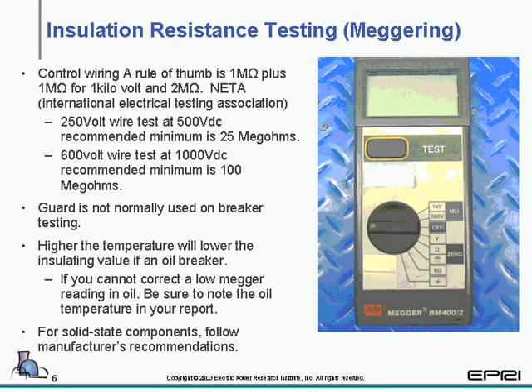When you start getting into control wiring, there tends to be some question as to what is acceptable. Most vendors require, as said, 2 megaohms, except NETA, the International Electrical Testing Association, has some criteria, and that is for 250 volt wiring, test at 500 volts DC, 25 megaohms at a minimum. And then for 600 volt wiring, test at 1,000 volts DC. At a minimum, you should see 100 megaohms. And keep in mind, solid state components follow the manufacturer recommendation.